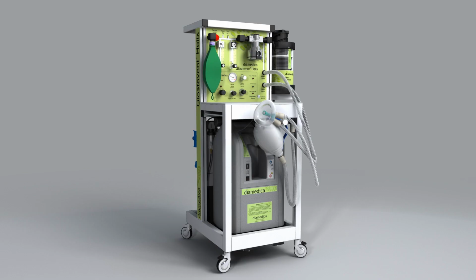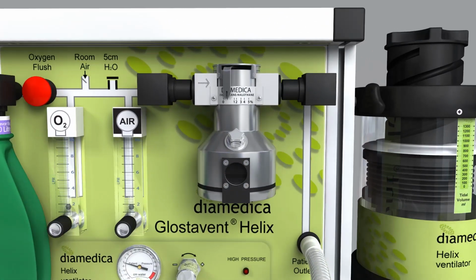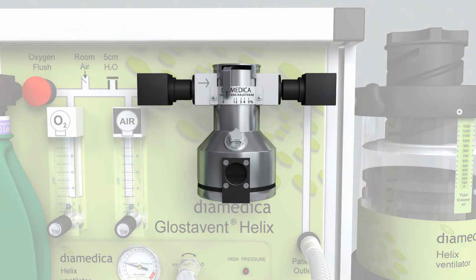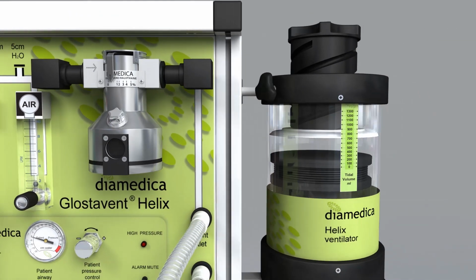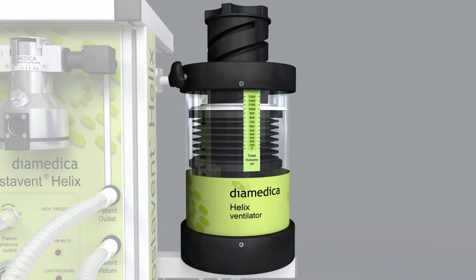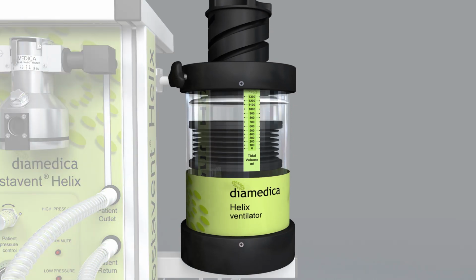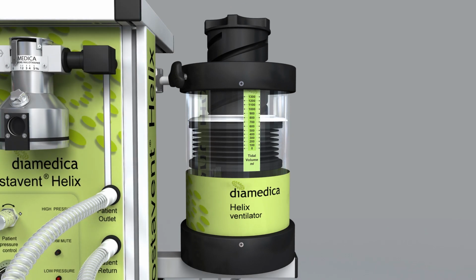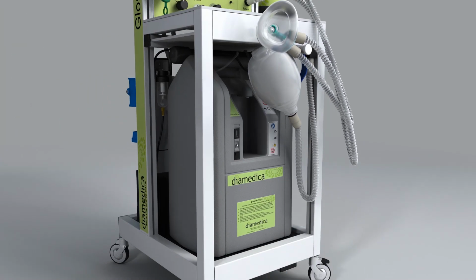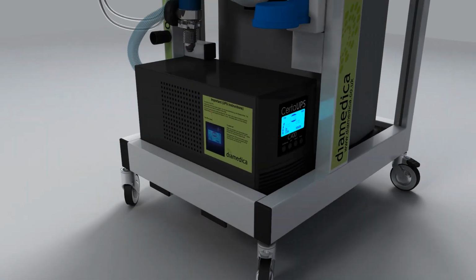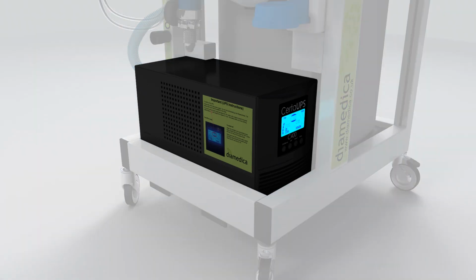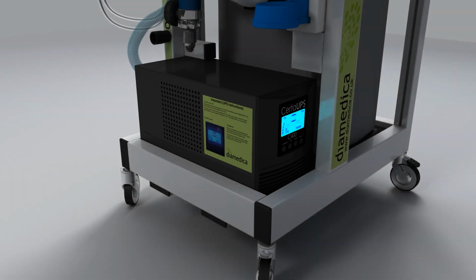The system consists of 4 main elements. The first element is a low-resistance, thermally stable vaporizer and breathing system, which allows the system to operate in continuous flow or in draw-over mode. The second is an efficient gas-driven ventilator suitable for adult and pediatric use that is located on the swing arm. The third element is an oxygen concentrator that produces medical oxygen and air from the atmosphere. The fourth element is an uninterruptible power supply, UPS, and battery backup support system which will provide power to the system if electrical power fails.